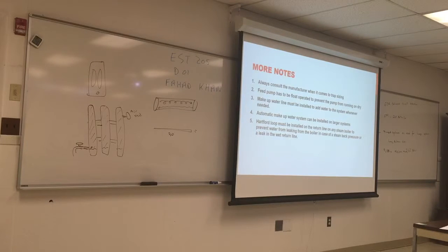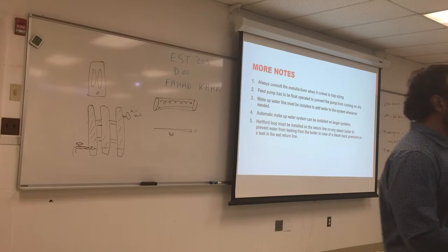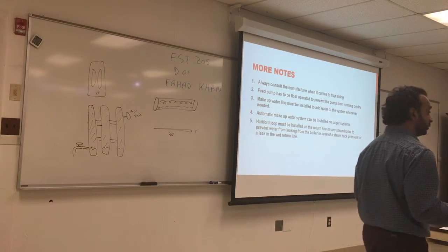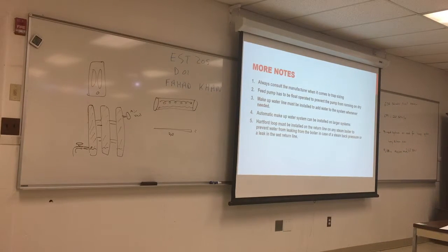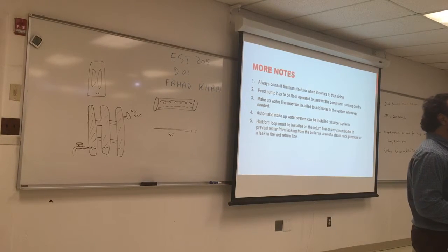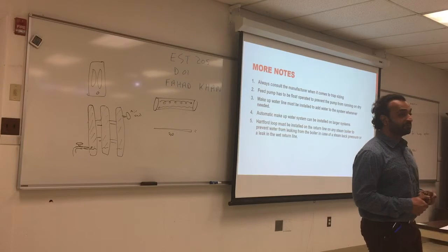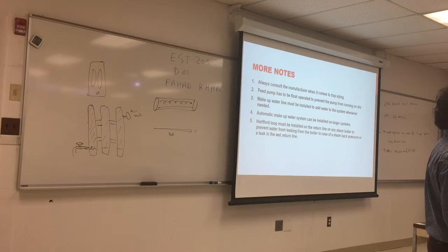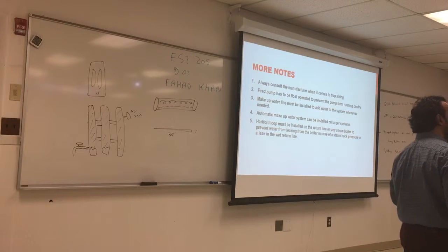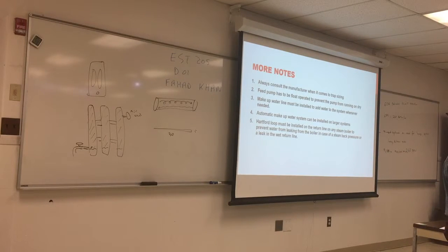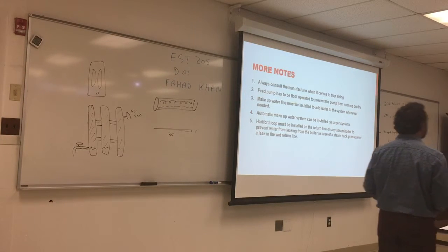So what do you do? Either you empty the entire boiler, wait for it to come to room temperature, then slowly introduce the water in. In some cases, if you have some experience, you can put a little bit of water in, 1 gallon at a time, and wait for it to mix. Do it gradually. Don't just crank up the water and drain the boiler. When you shock the system, it will crack. This is something that happened to some people with cars in the 70s and 80s, where the car overheats and all the steam comes out, and somebody comes in with cold water and pours it in the radiator, and that's when you crack your engine block, and you have to change the engine.